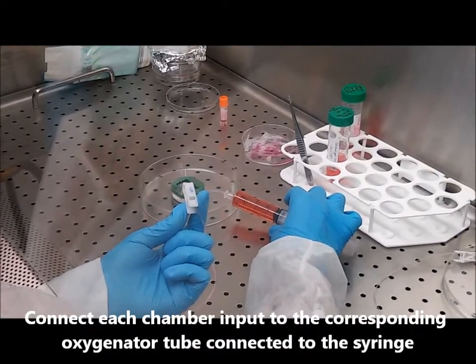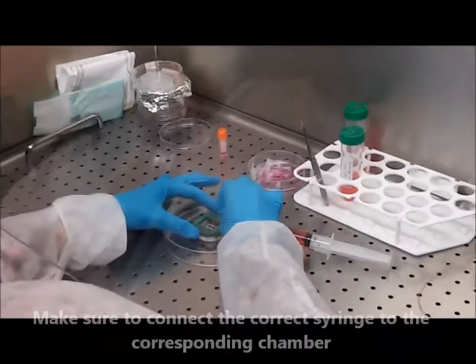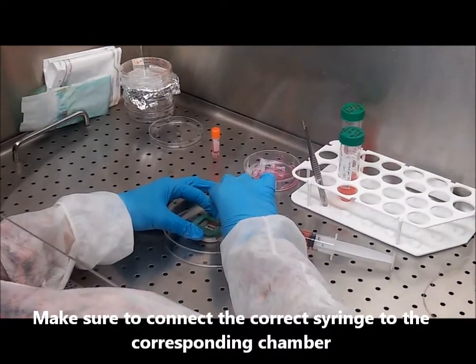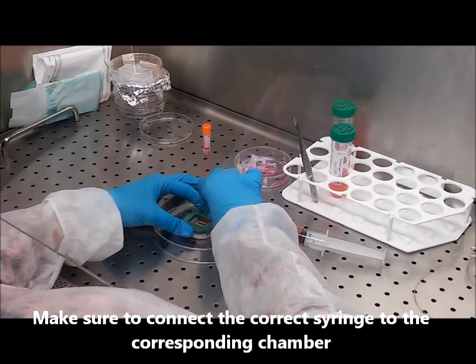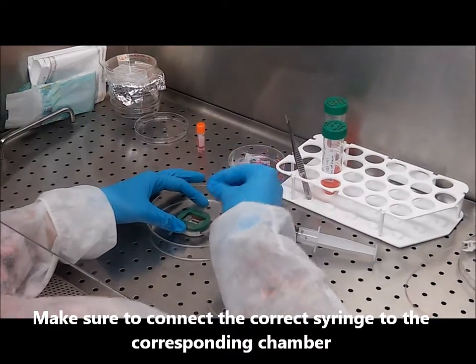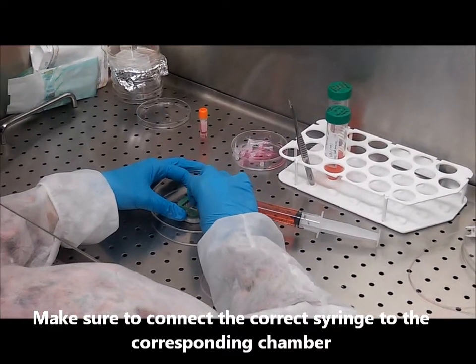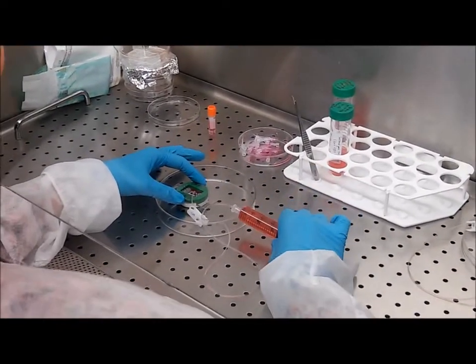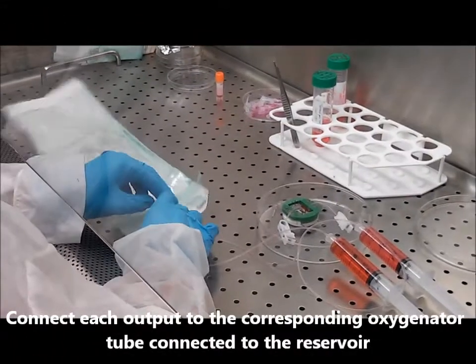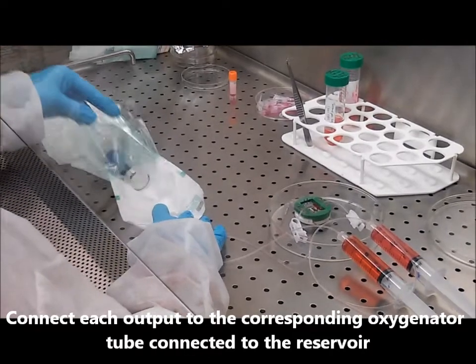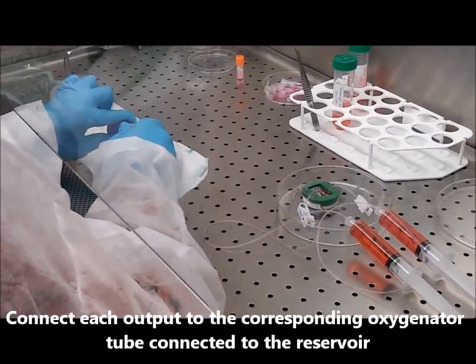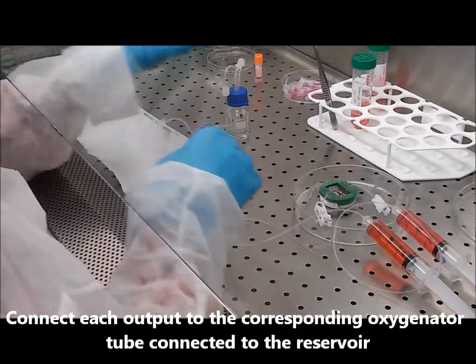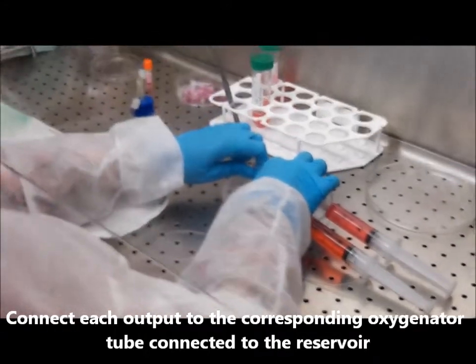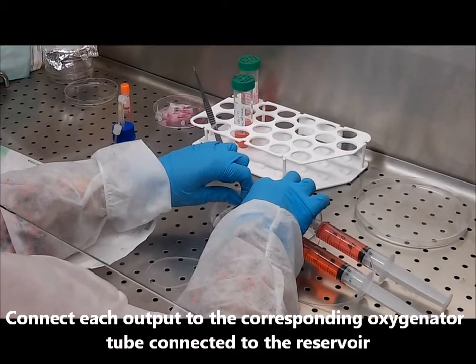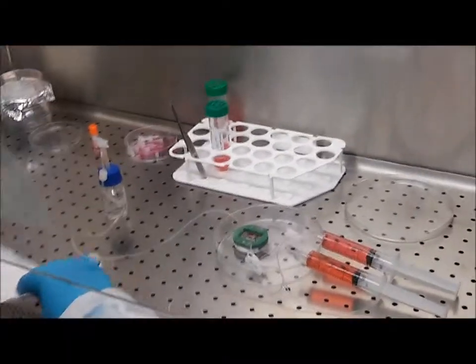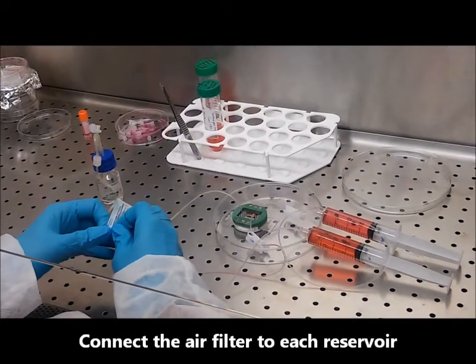Connect each chamber input to the corresponding oxygenator tube connected to the syringe. Make sure to connect the correct syringe to the corresponding chamber. Connect each output to the corresponding oxygenator tube connected to the reservoir. Connect the air filter to each reservoir.